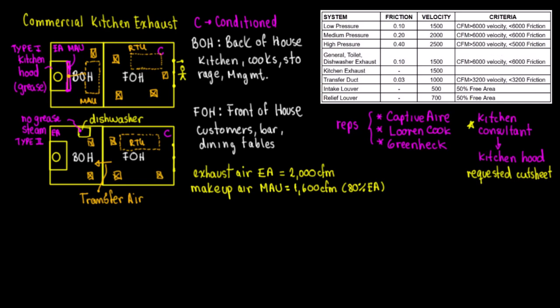It's important to think about it. You might be wondering, wait a minute, what's going on with my 80% of the exhaust air rule in here? Whenever you're doing transfer air or an RTU and you don't have a makeup air unit, you're just adding outside air to your rooftop unit mixed air. So I would recommend that you do this. I'm going to put this in white. This is an air balance schedule. You need to check how your balancing is. I'm going to make an example very quickly in here.